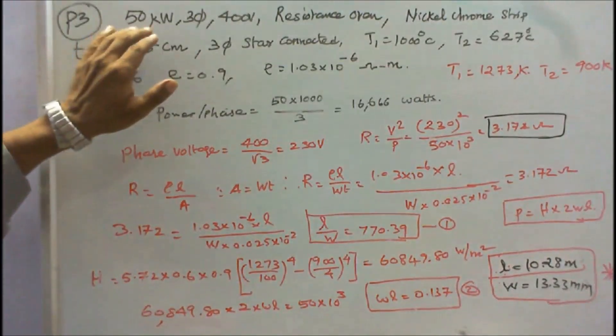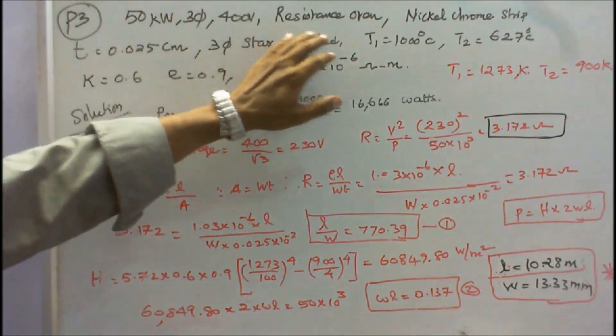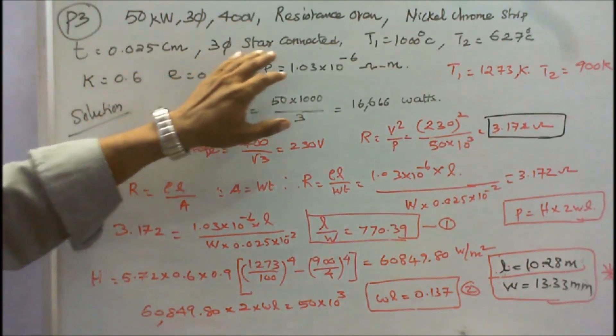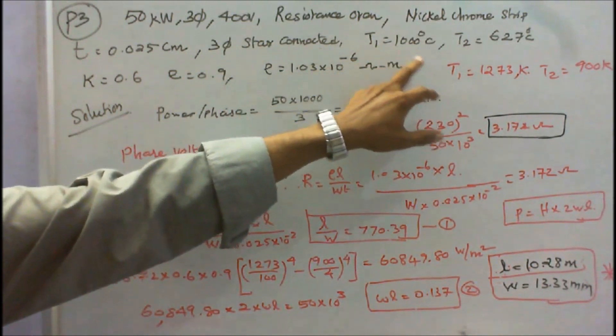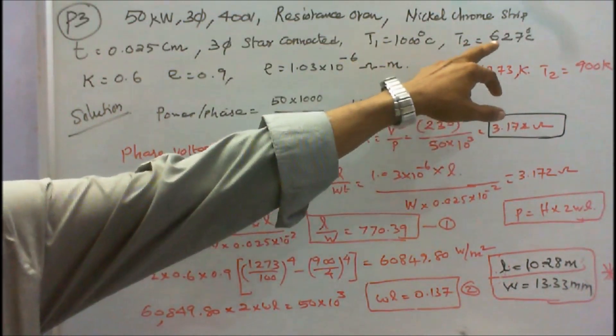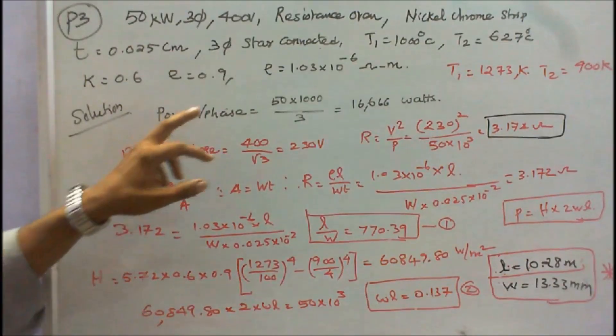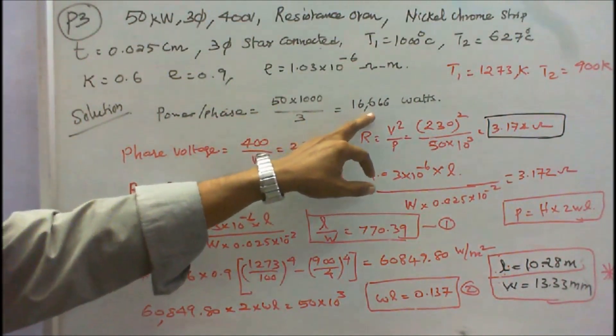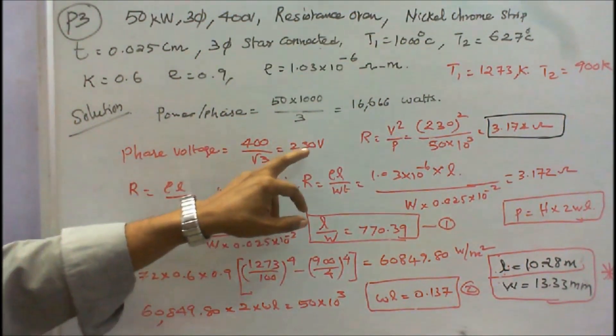In this problem, input power is 50kW, three-phase 400V resistance oven, nickel-chrome strip, thickness is 0.025 cm, three-phase star-connected. T1 equals 1000°C, so T1 equals 1000 plus 273 equals 1273 Kelvin. T2 equals 627°C, so T2 equals 627 plus 273 equals 900 Kelvin. Power per phase equals 50×10³ divided by 3 equals 16,667 watts. Phase voltage equals 400 divided by √3 equals 230 volts.